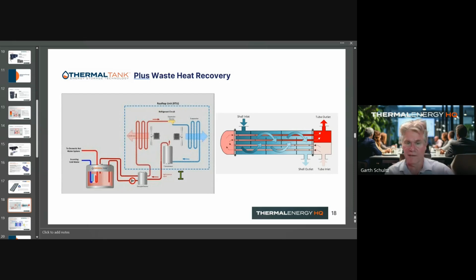In a refrigeration cycle associated with the chiller, you can add a mechanism just after the compressor output called partial heat recovery. People call them desuperheaters, and it takes that hot refrigerant and, through a flat plate heat exchanger system, allows you to build thermal potential for use in processes, domestic hot water, or other uses in your facility. It can be built in and spec'd as part of the chiller assembly, or grafted in as an aftermarket assembly. But your best direction is to have it spec'd in when your new chiller comes into place—that gives you cooler refrigerant temperatures so the condenser side of your operation runs easier on your rooftop unit or chiller.